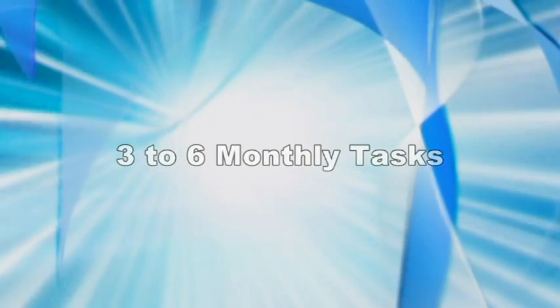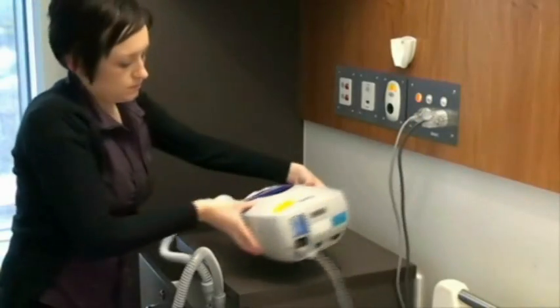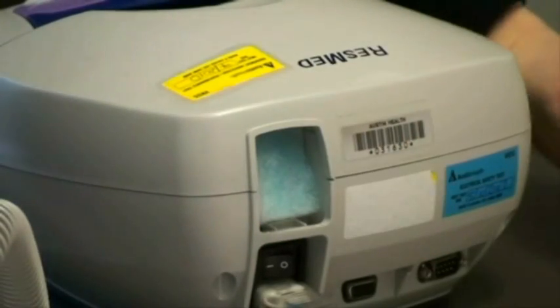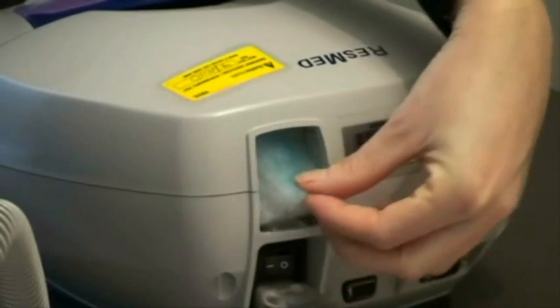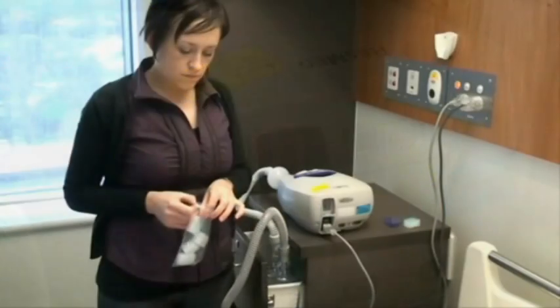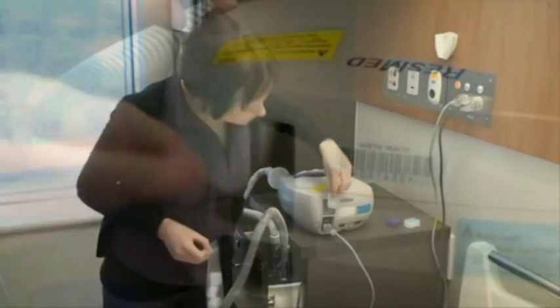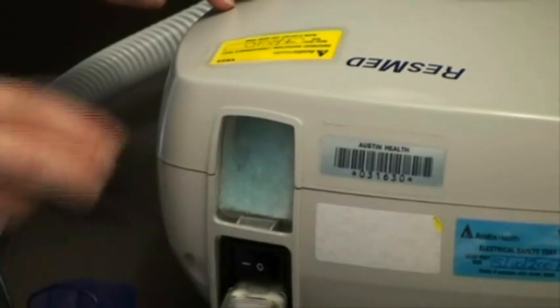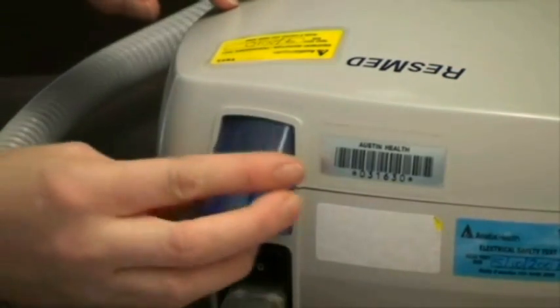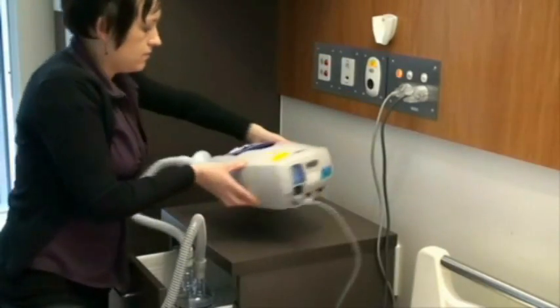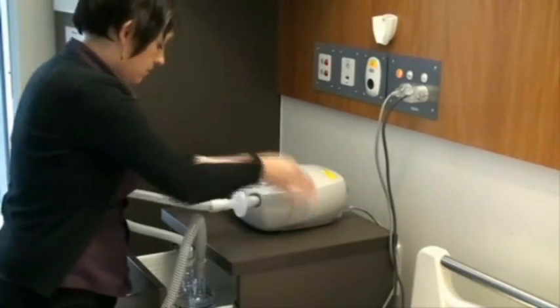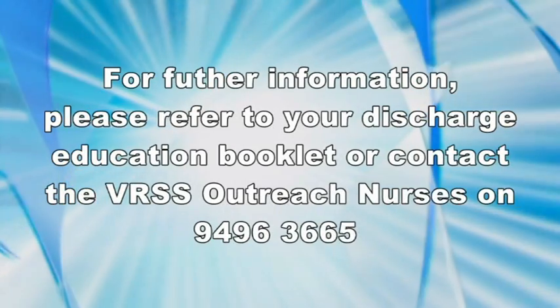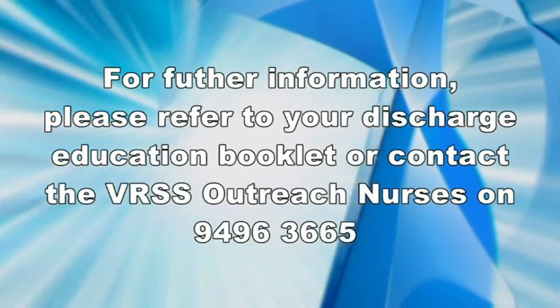3 to 6 monthly tasks. The ventilator dust filter is located at the back of the machine and should be replaced approximately every 3 months. To change, remove the filter cover on the back of the machine. Remove and dispose of the old dust filter and insert a new filter, with the blue tinted side facing outwards. Replace the air filter cover. For further information, please refer to your discharge education booklet or contact the VRSS outreach nurses.